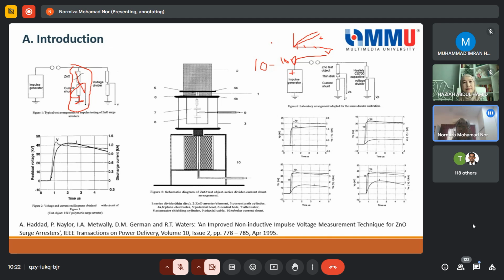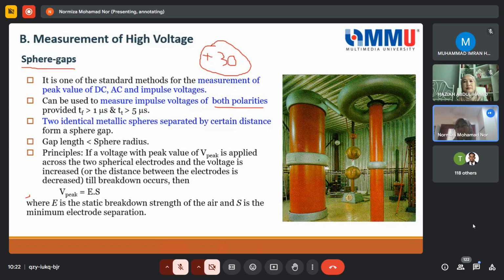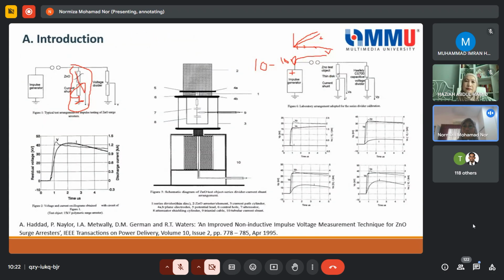Because it relies on the air breakdown. In other words, the breakdown voltage, the breakdown between this gap here. This gap is of course air, and we know that air breakdown can be influenced by the impulse polarity. That's why it says here that it can measure for both impulse polarities, but later you will find that the disadvantage of the sphere gap is that it is very much affected by the polarity, as what you've seen here. You apply the same voltage, but when you measure at positive, you will find that the voltage reading is lower than the negative, even though you apply the same voltage level.